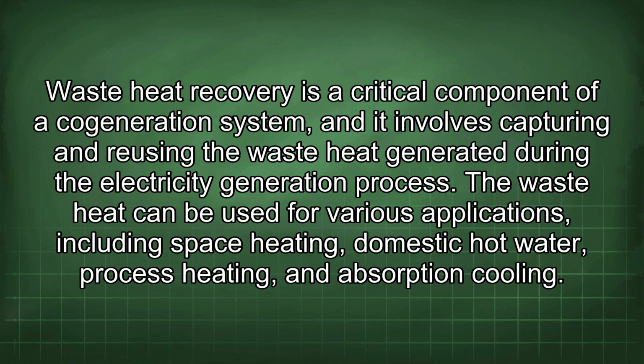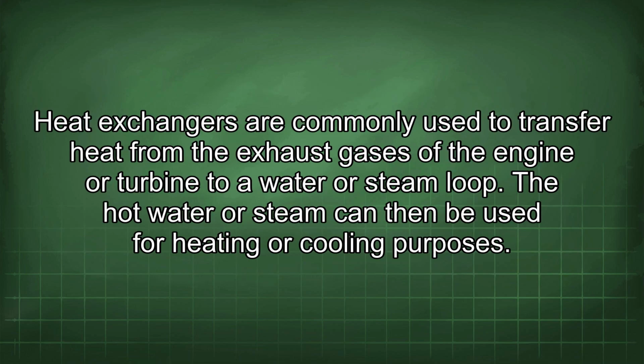Waste heat recovery is a critical component of a cogeneration system, involving capturing and reusing the waste heat generated during electricity generation. The waste heat can be used for space heating, domestic hot water, process heating, and absorption cooling. Heat exchangers are commonly used to transfer heat from the exhaust gases of the engine or turbine to a water or steam loop, which can then be used for heating or cooling purposes.